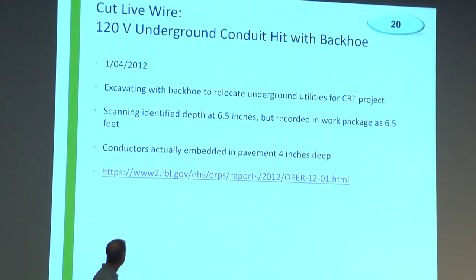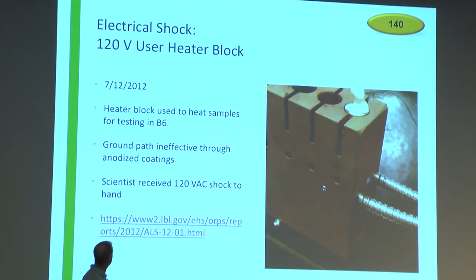So here's a series of incidents. This one here, we cut into a live wire with a backhoe. Here was a researcher, they had a little heater block. It shorted to ground, and even though the system was supposedly grounded, the ground path was not valid. There was no GFCI either.